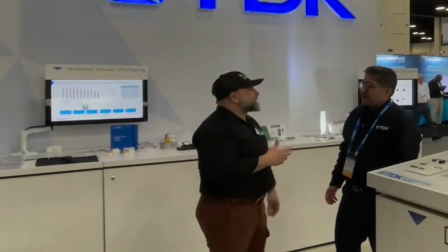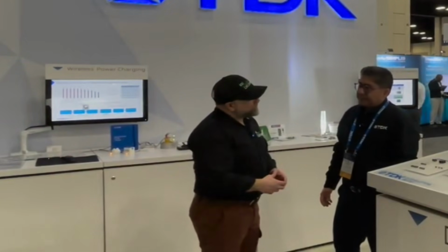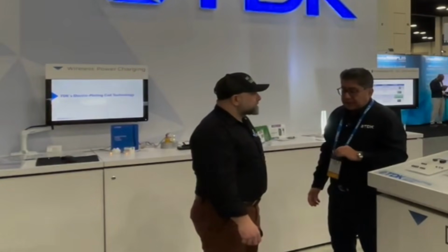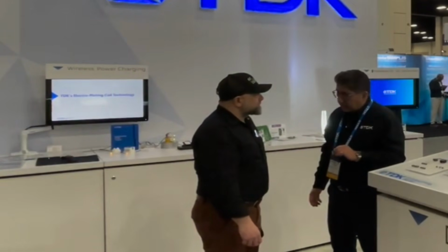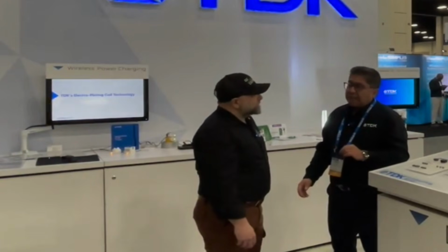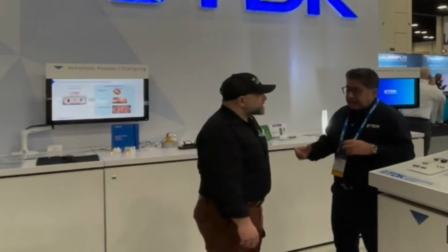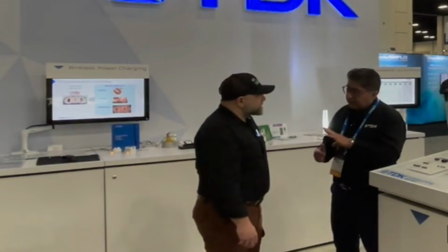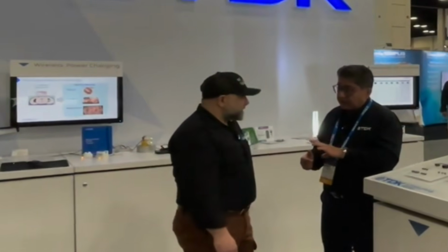Annie Van, there's still some design challenges with SSTs. So what are some of the most difficult for engineers? The single most design challenge which SST manufacturers are facing at the moment is on the medium voltage high frequency transformer, because inside that, as per design rule, you need to have 3 times the insulation voltage. So we are talking about 100 kilovolt of insulation. This is the challenge.